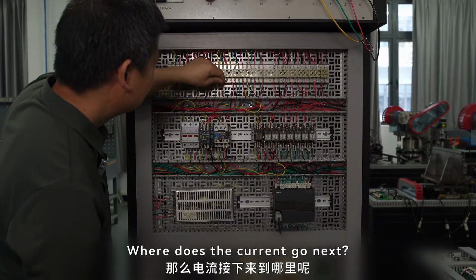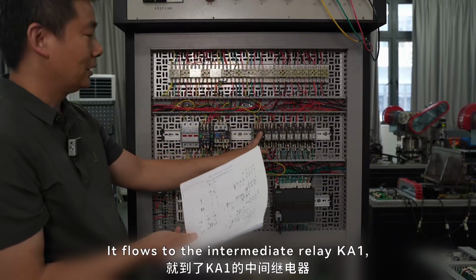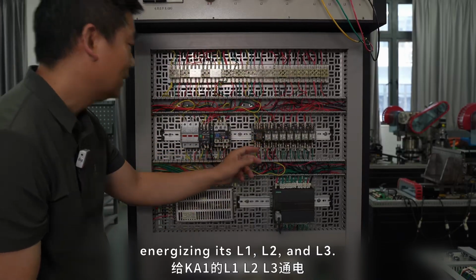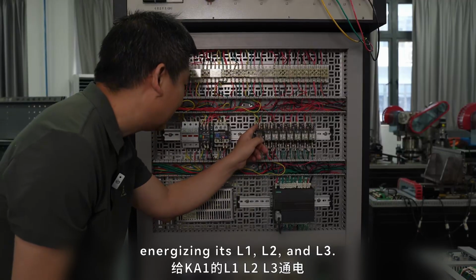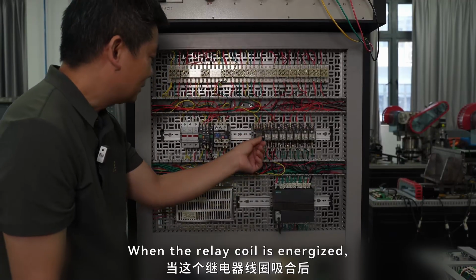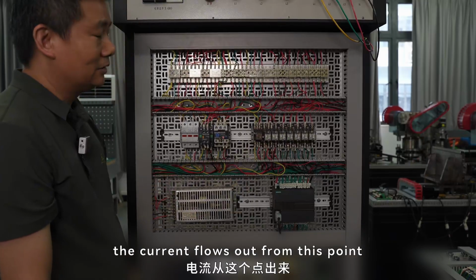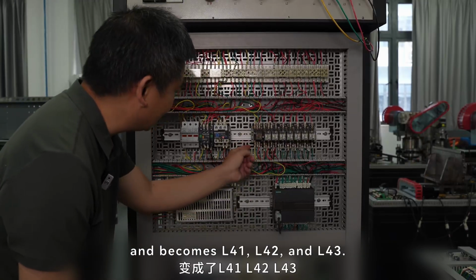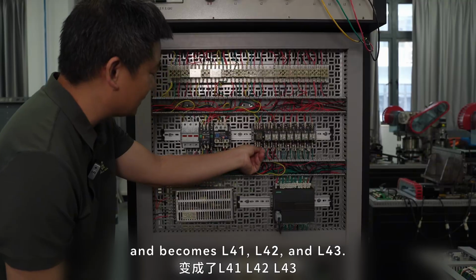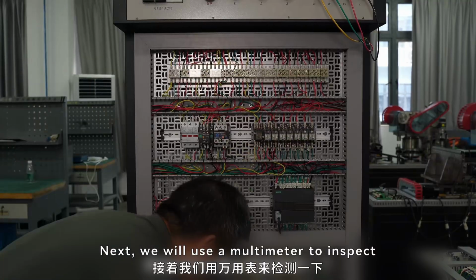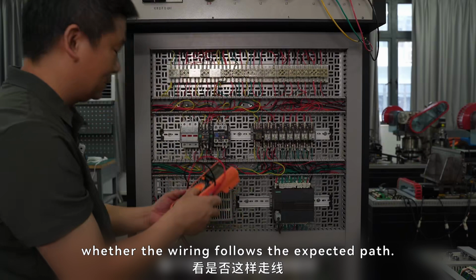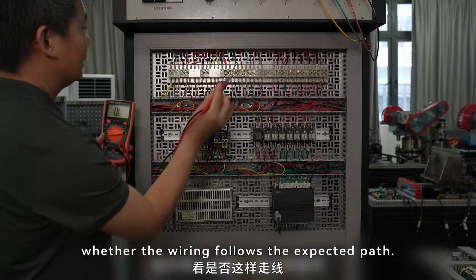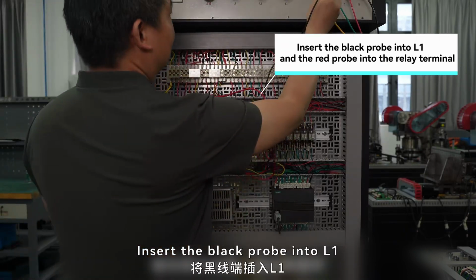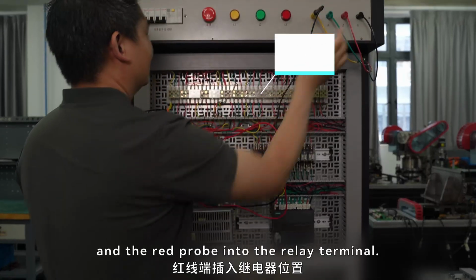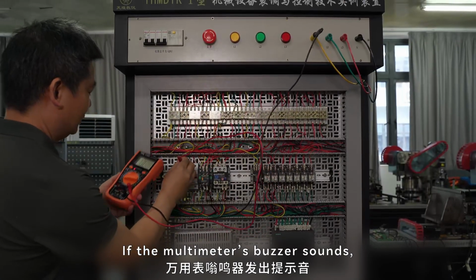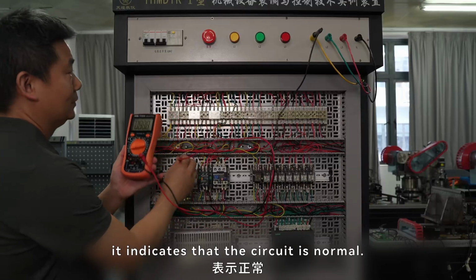Where does the current go next? It flows to the intermediate relay KA1, energizing its L1, L2, and L3. When the relay coil is energized, the current flows out from this point and becomes L41, L42, and L43. Next, we will use a multimeter to inspect whether the wiring follows the expected path. Insert the black probe into L1 and the red probe into the relay terminal. If the multimeter's buzzer sounds, it indicates that the circuit is normal.